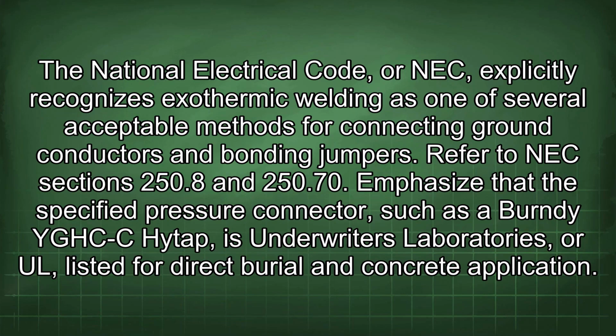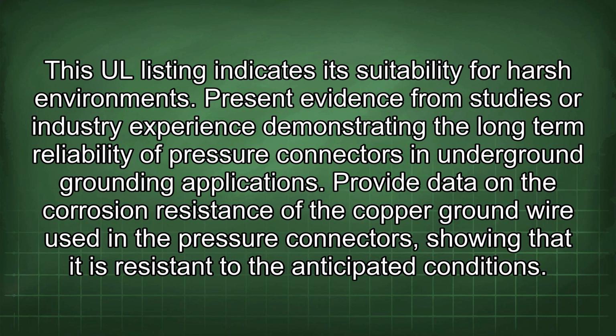The National Electrical Code, or NEC, explicitly recognizes exothermic welding as one of several acceptable methods for connecting ground conductors and bonding jumpers. Refer to NEC sections 250.8 and 250.70. Emphasize that the specified pressure connector, such as a Burndy YGHC-C Hytap, is Underwriters Laboratories, or UL, listed for direct burial and concrete application.